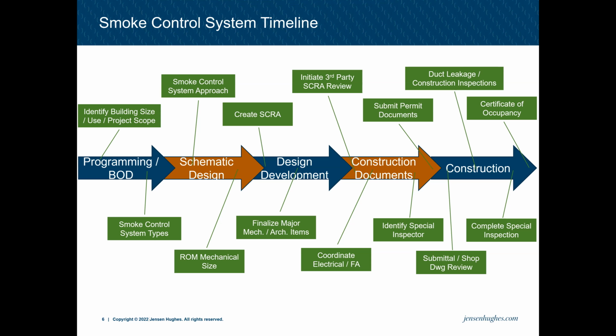From there, the project will move into a schematic design phase. And ideally in that phase is when you first figure out the smoke control system approach. So if it is a new high-rise system, you're figuring out, are we going to inject air from the top of the stair or multiple point injection throughout the height of the stair? If it's an atrium, how are you providing makeup air? How are you providing exhaust?